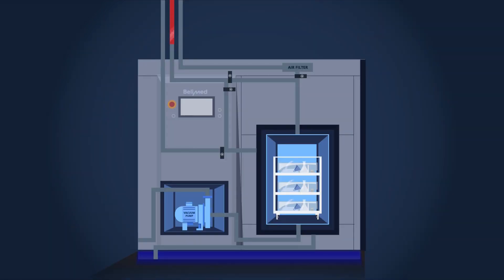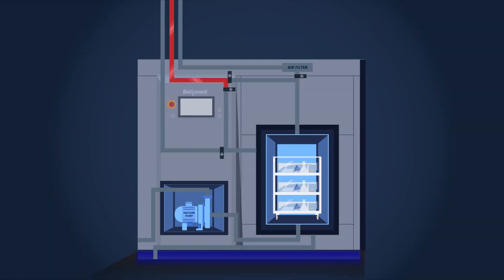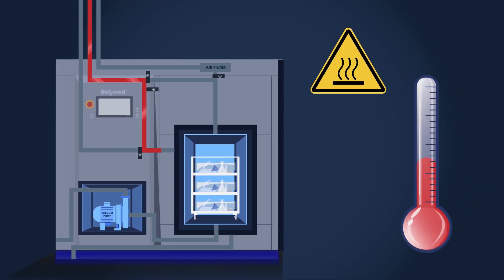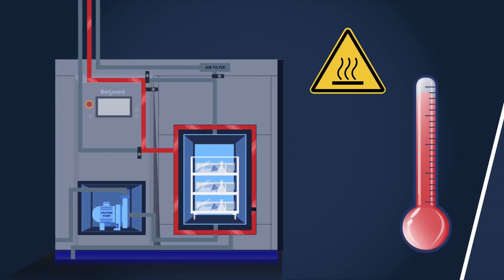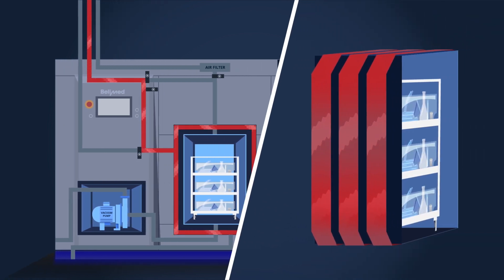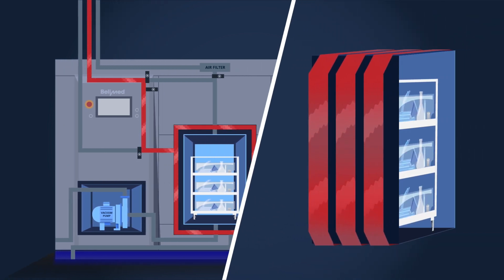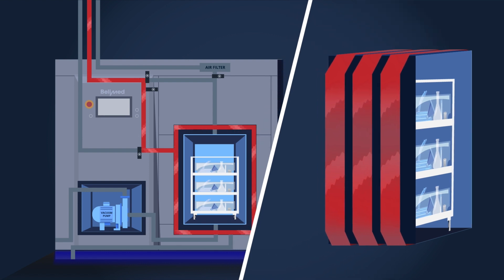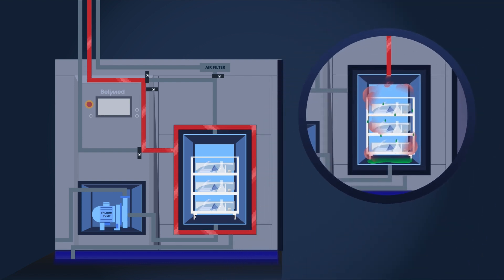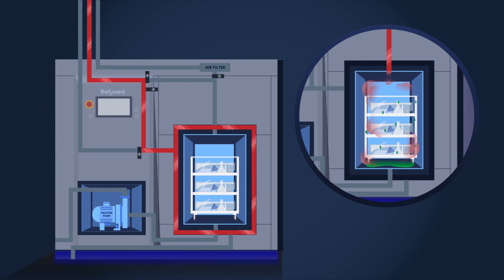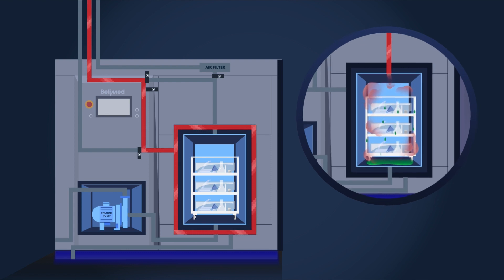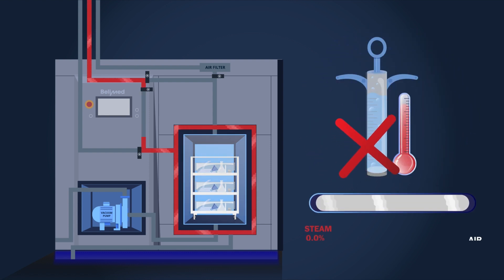First, the chamber walls must be heated up. Therefore, steam is passed through the channels outside the chamber. If the walls are not heated first, the steam needed later inside the chamber for sterilization would condense and cause the products to be sterilized to become wet.